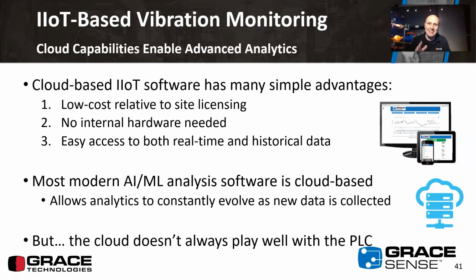The problem with that in the industrial environment is that the cloud piece doesn't always play well with the PLC. It's vitally important, and pretty much all the customers we talk to confirm this, that if we're going to do IoT-based vibration monitoring in an industrial facility, we have to be able to get that data, or at least the processed results, back to the PLC so it can work in the same paradigm as the rest of those industrial systems.